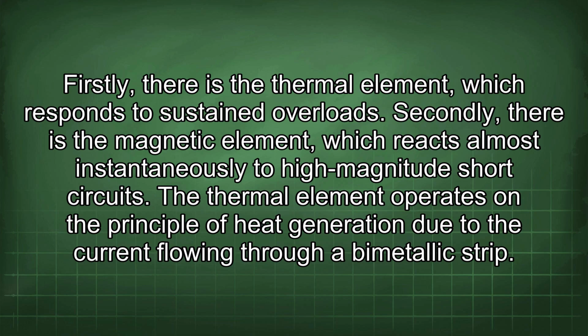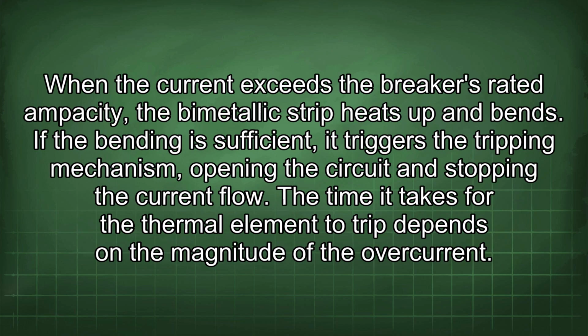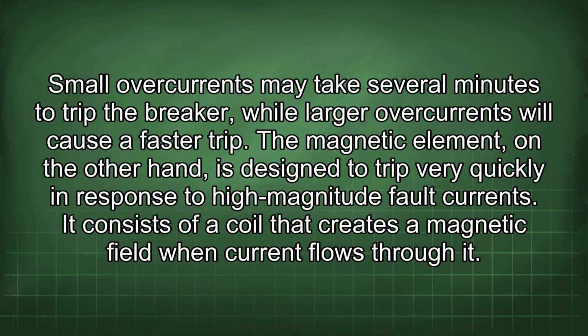The thermal element operates on the principle of heat generation due to the current flowing through a bimetallic strip. When the current exceeds the breaker's rated ampacity, the bimetallic strip heats up and bends. If the bending is sufficient, it triggers the tripping mechanism, opening the circuit and stopping the current flow. The time it takes for the thermal element to trip depends on the magnitude of the overcurrent. Small overcurrents may take several minutes to trip the breaker, while larger overcurrents will cause a faster trip.